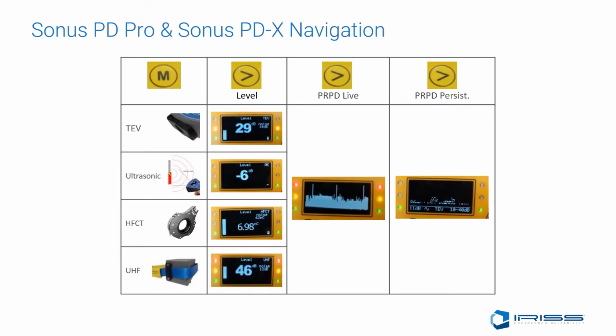With each mode offering 3 views for the inspector to review the information received with the Sonus PD Pro and Sonus PDX devices, the inspector can switch from a spot test, which will display the decibels being received in TEV, ultrasound, and UHF mode, and in picocoulombs while operating in the HFCT mode. These screens will allow the inspector to see the intensity of the anomalies present in the asset or being emitted from the cabinet while testing energized gear.